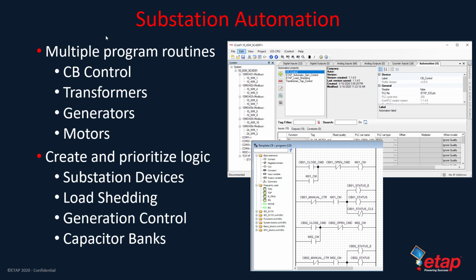And then finally, we have the Substation Automation. The objective of the Substation Automation is to provide an interface to the user where they can create programs using an IEC 61131 standard to define control on your substation. Now, the standard includes programming in one of the formats, which is ladder logic, but you can also create other programs like in text, function blocks, or any of the covered standards. In this case, we're putting here a couple of examples of the programs.